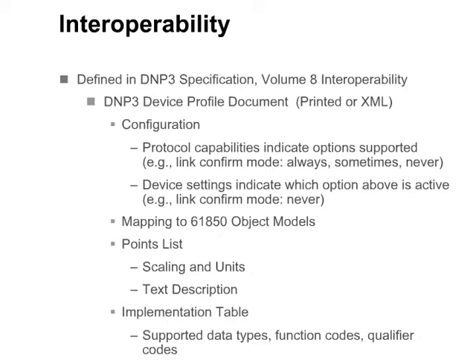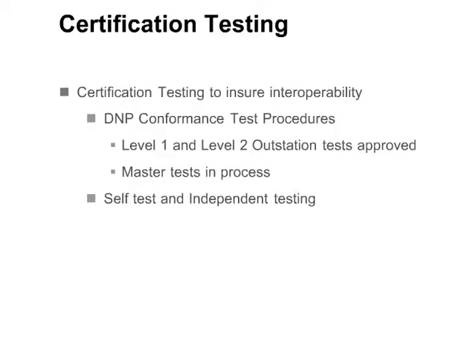The device profile document provides a point list, which includes scaling, units, and a text description. It also includes an implementation table, which indicates the supported data types, function codes, and qualifier codes. Certification testing is designed to promote interoperability. This allows utilities to use equipment from different manufacturers with a high degree of confidence that the equipment will work together.